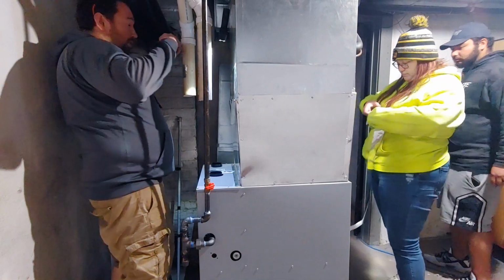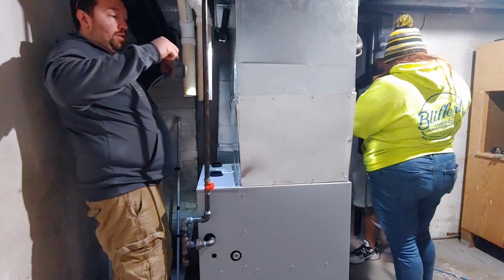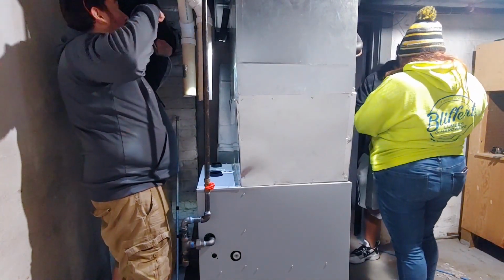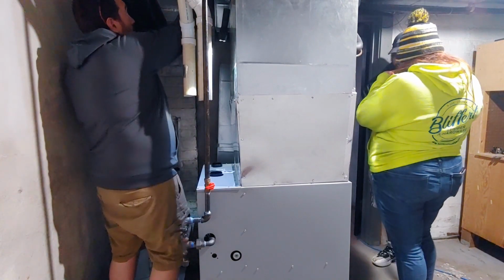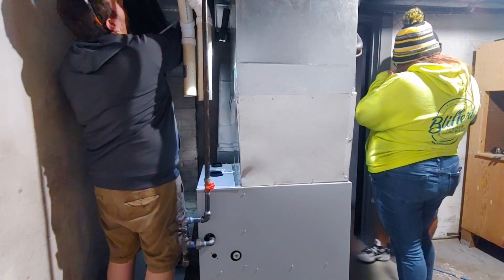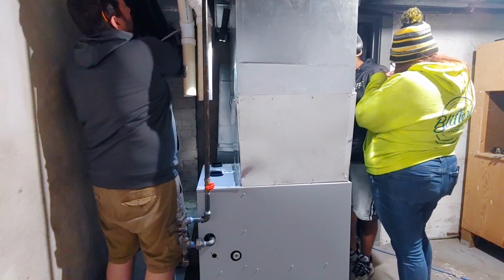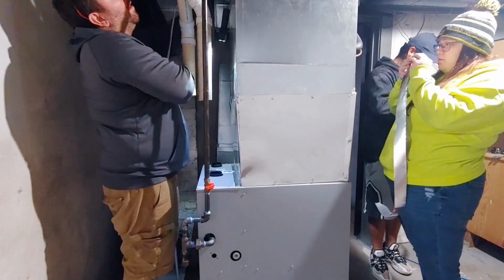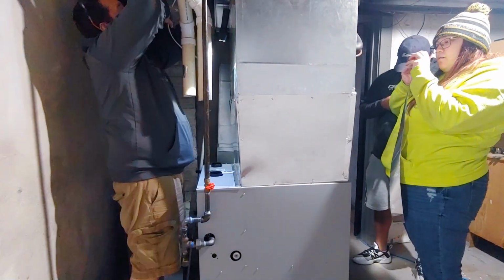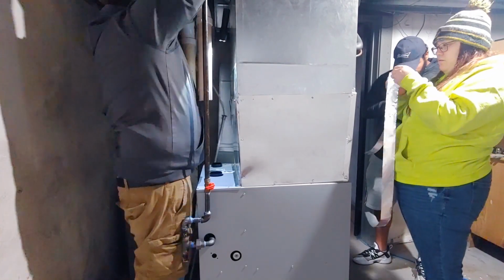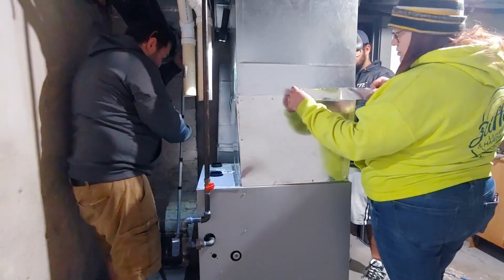What I have in my hand is some new Romex down a conduit drop to the switch. The wire is going to go up and over the ductwork. I'll staple it to the joist and connect it into a better junction box, and then the drop will come down to the switch, which I'll wire into the furnace.